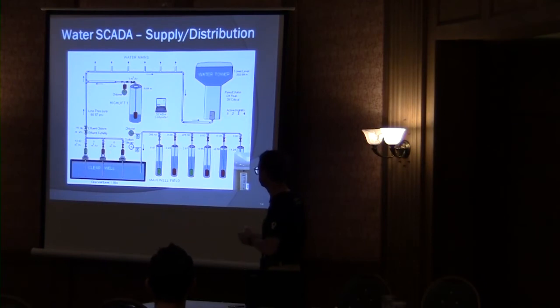So you pump the water from the plant, from the clear well, through the high lift pumps, add the chlorine, but you also monitor the chlorine. They put the SCADA computer here, okay. And we also had 2 well fields, so you could draw water from the well fields, and you want to keep control of all that. So that's what the SCADA does. It gives you readouts on it. Again, back at that one computer screen, you can go to different screens that show, here's all the wells, here's the tank, and you can drill down into them as well.